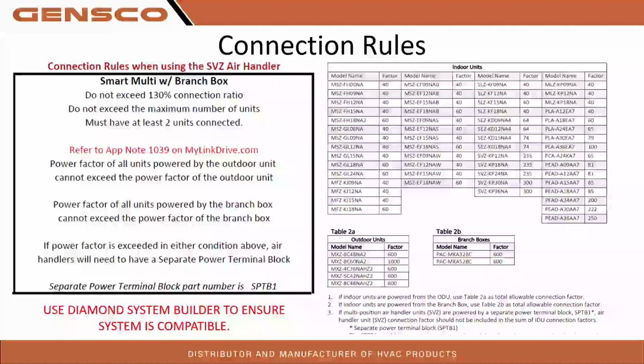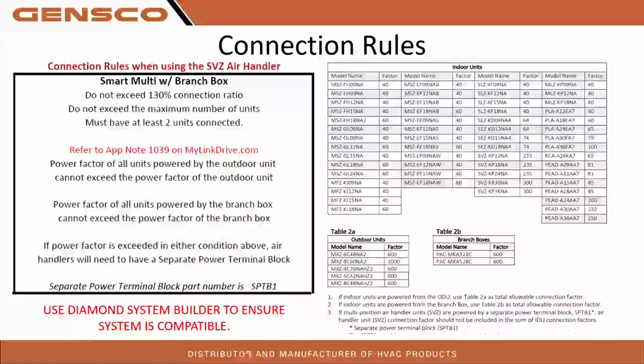Connection rules. If you are using a branch box, there are some connection rules for the amount of power draw that your indoor equipment can handle. This is actually an app note that you can find on mylinkdrive.com under the app notes. It's app note 1039, and what you're going to find on this is covering power factors for the branch box. All of your equipment does have a power factor associated with it right here. I know this table is a little bit older. It's for the older 8C and 4C equipment, but Smart Multi is still the same thing, and your indoor equipment is still going to be the same as well.